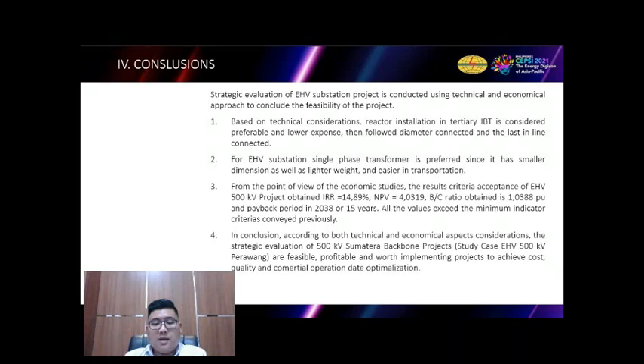Second, for EHV substation, single-phase transformer is preferred since it has smaller dimension as well as lighter weight and is easier in transportation. Third, from the point of view of economic studies, the acceptance criteria results of the EHV 500 kV project obtained IRR of 14.89%, the NPV of 4.0319, BC ratio of 1.0388 per unit, and the payback period in 2038 or 15 years later. All the values exceed the minimum indicator criteria conveyed previously.